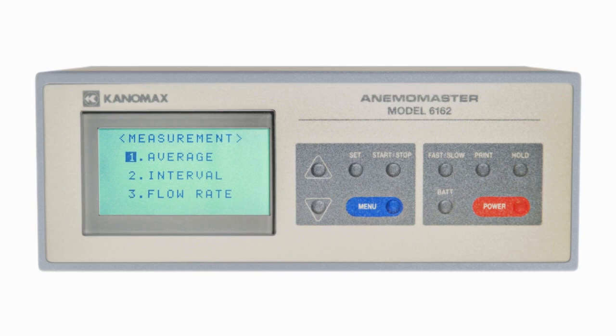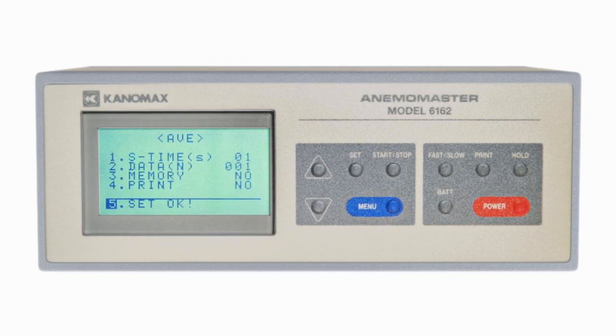Selecting average in the measurement menu will show you the options you have for configuring your reading. S-time represents the sampling time in seconds. Data represents the number of times you want to sample. Memory is for selecting whether you want the data to be stored to the local storage on the anemometer. And print is for having the anemometer print out the calculation results via a connected printer.